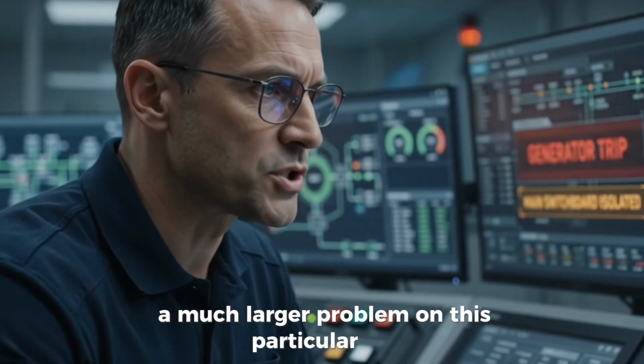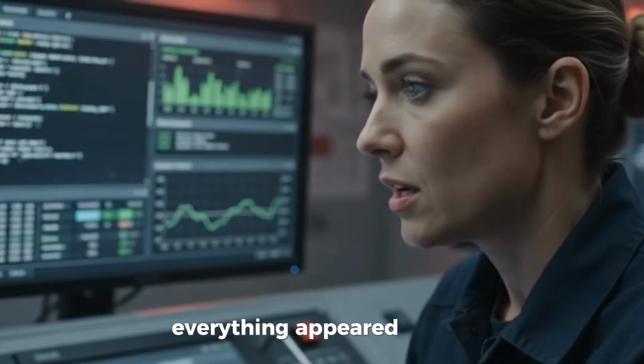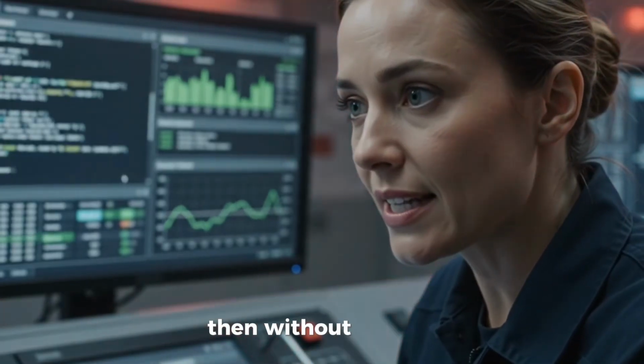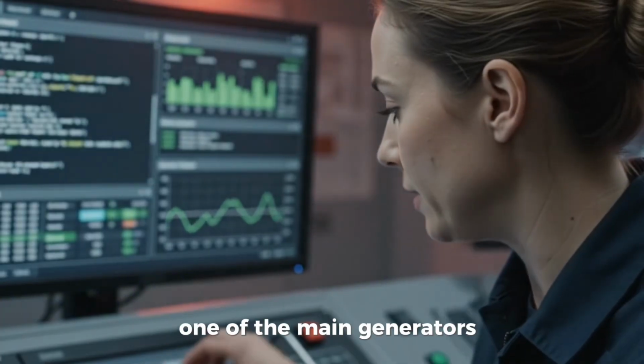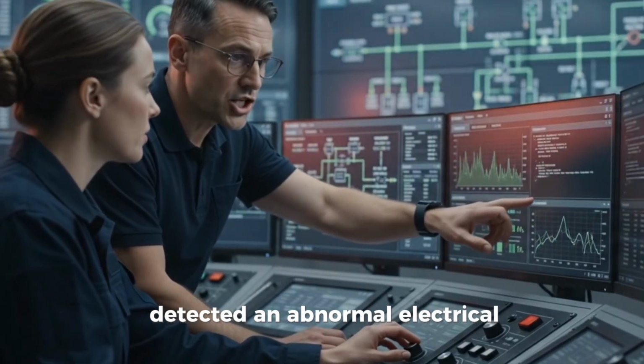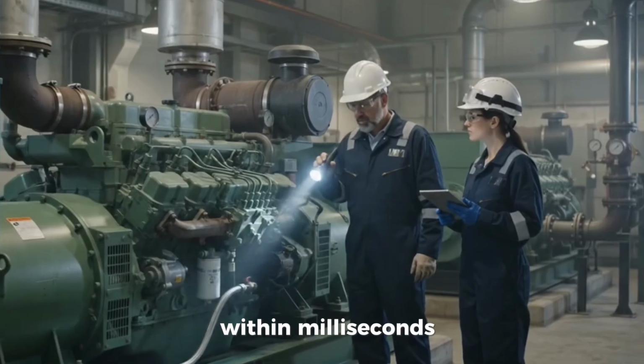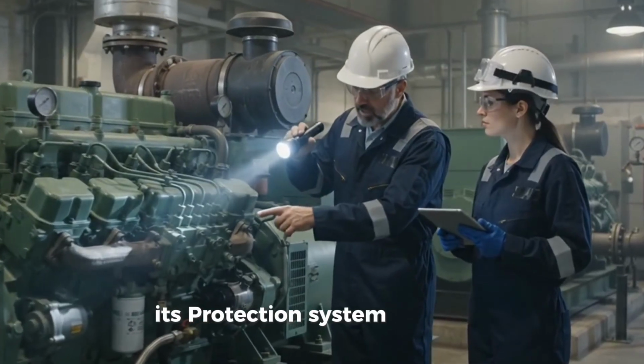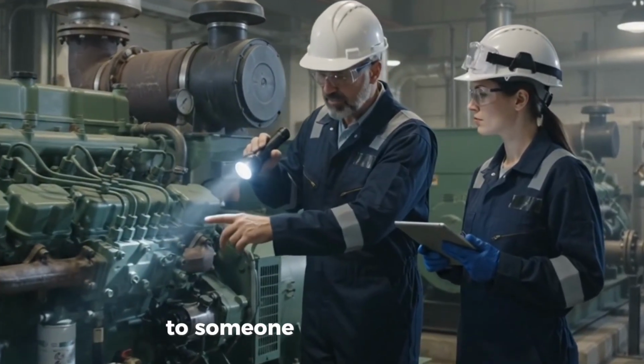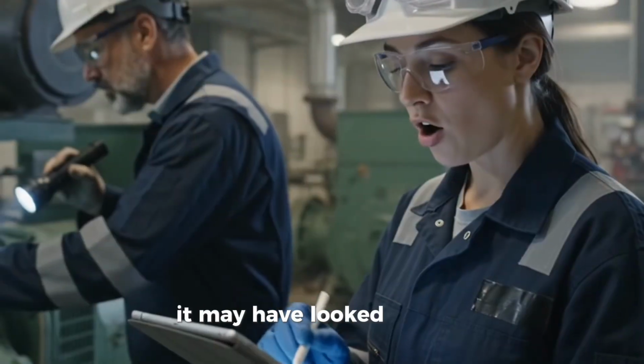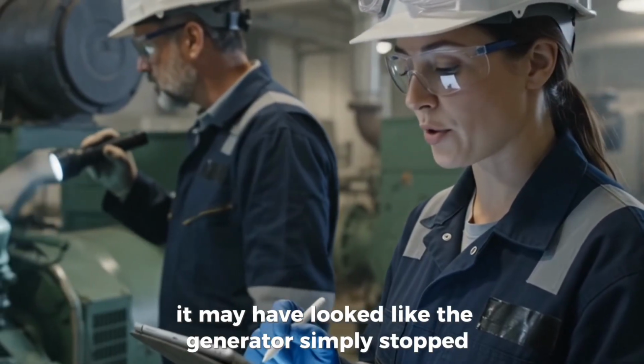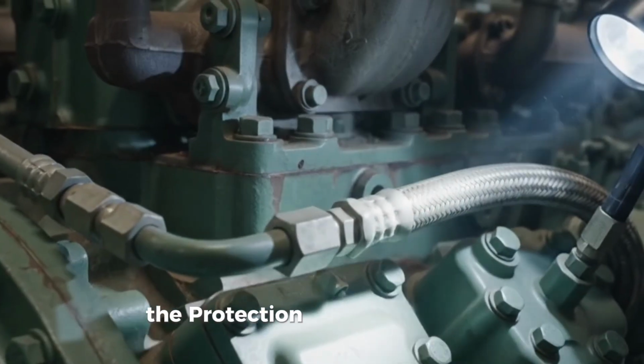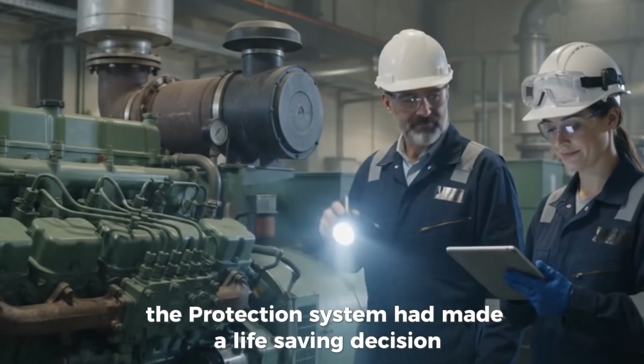On this particular day, everything appeared normal. Then, without warning, one of the main generators detected an abnormal electrical fault. Within milliseconds, its protection system activated automatically. To someone standing on deck, it may have looked like the generator simply stopped, but in reality, the protection system had made a life-saving decision.